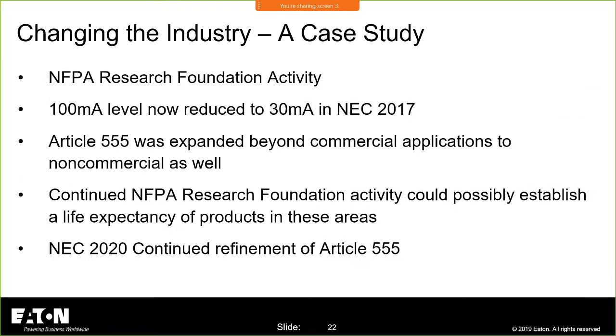The NFPA Research Foundation kicked off some studies. They looked at the 100 milliamp threshold and said we need to lower that to 30 milliamps on all overcurrent devices feeding the marina, which then became problematic—we had to do a TIA to fix that. Now we're back to 100 milliamps feeding the marina, 30 milliamps feeding the boat, 4 to 6 milliamps feeding receptacles. We're going to talk about that this week. We also had a task group associated with this, where we expanded Article 555 beyond commercial to non-commercial as well, back to where it used to be.